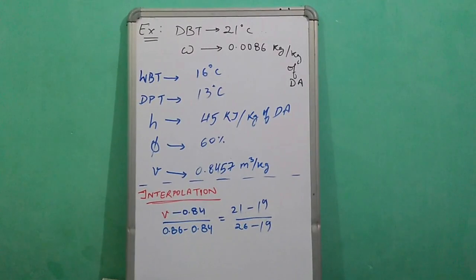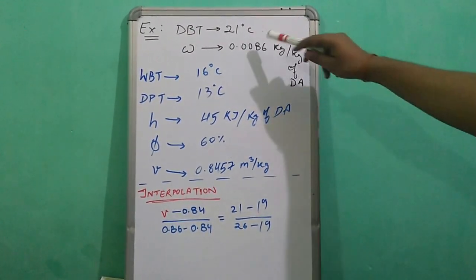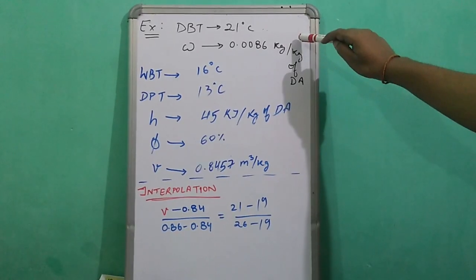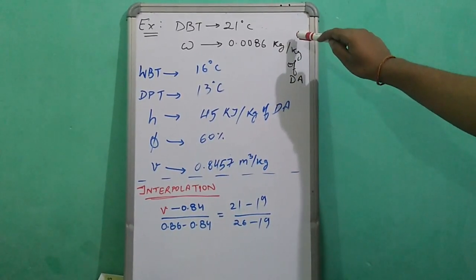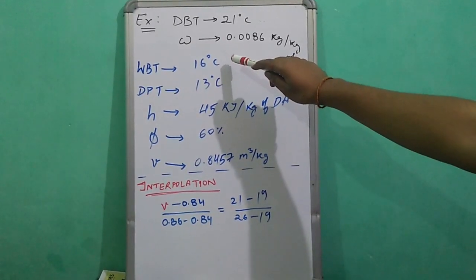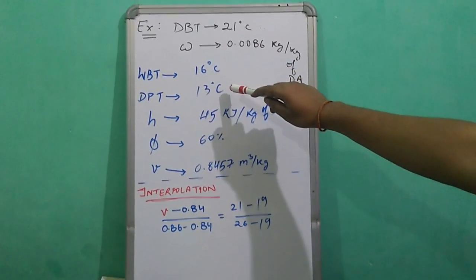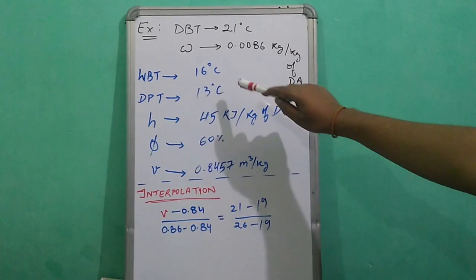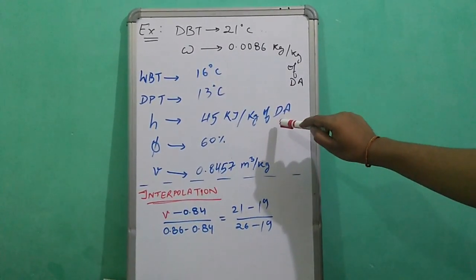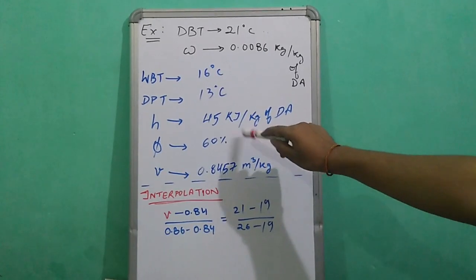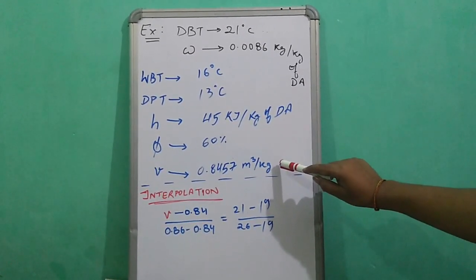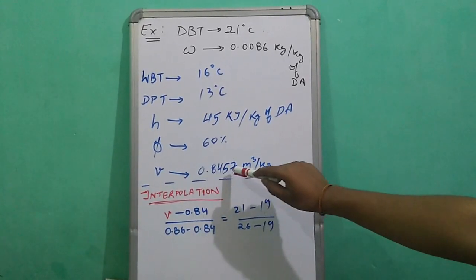Let's take an example. At a dry bulb temperature of 21 degrees Celsius and a specific humidity of 0.0086, we get a wet bulb temperature of 16 degrees Celsius, a dew point temperature of 13 degrees Celsius, an enthalpy of 45 kilojoules per kg of dry air, a relative humidity of 60%, and a specific volume of 0.8457.